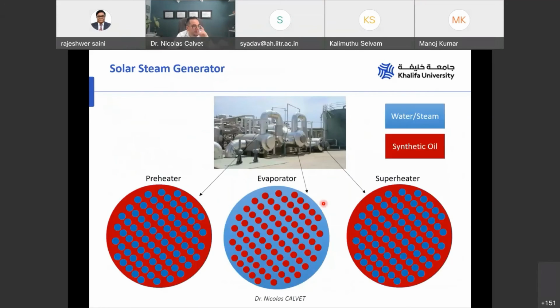So basically, how it works, this is a cross section. You have a pipe where the water is circulating, and around the pipe you have synthetic oil. So you preheat the water here, and then in the evaporator, it's the contrary. You have the oil in the pipe, and the water is around the pipe to let the water evaporate and get the steam. And in the superheater, it's again the contrary. The steam is under pressure inside the pipe, and the oil is around the pipe. So it's a very conventional heat exchanger, but you have to be careful to never mix water with oil, or the contrary.